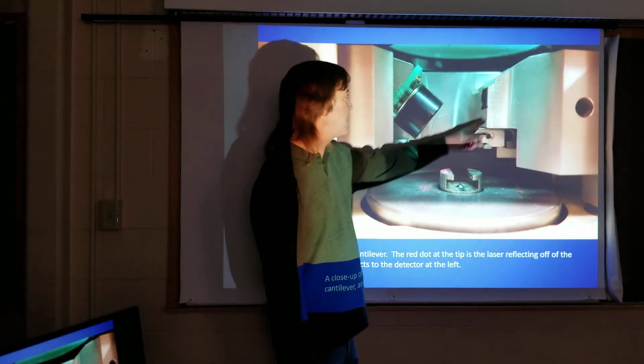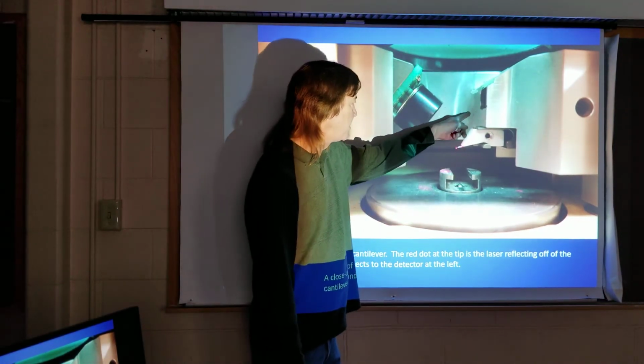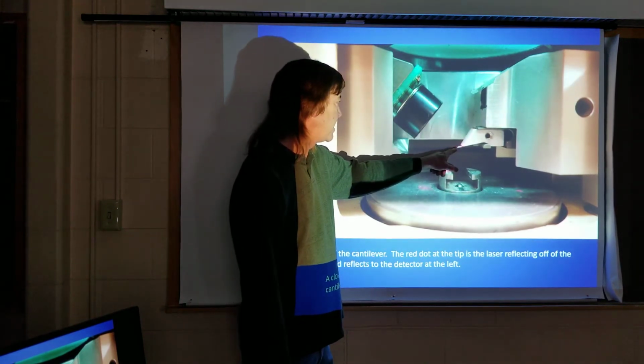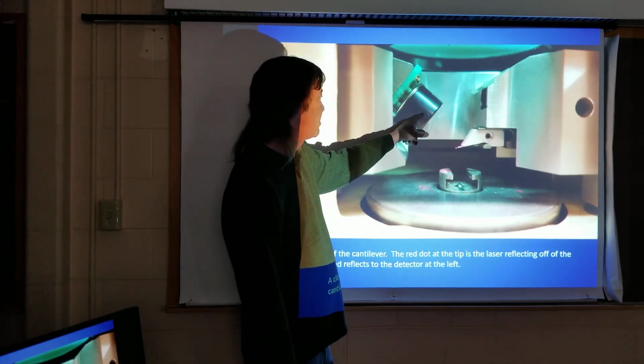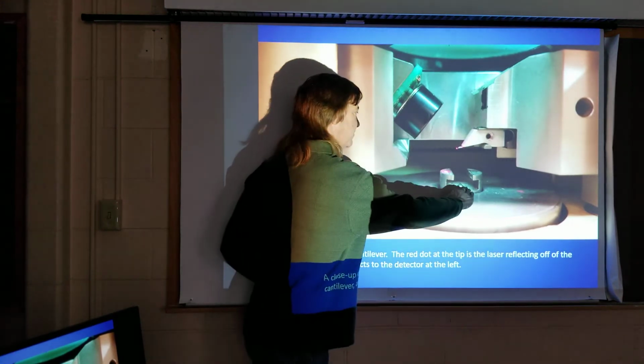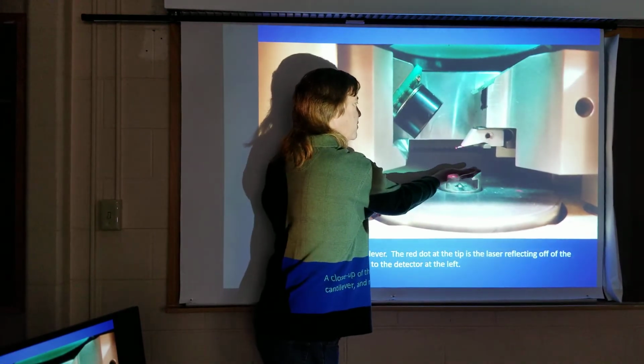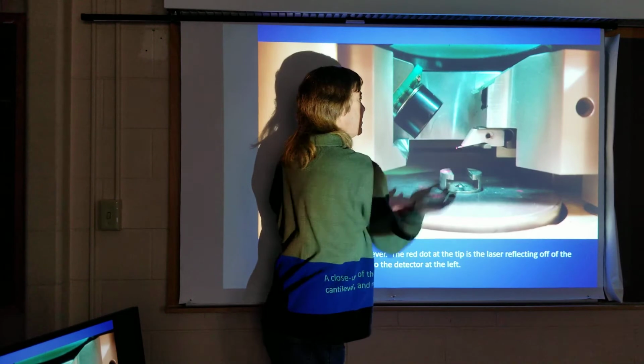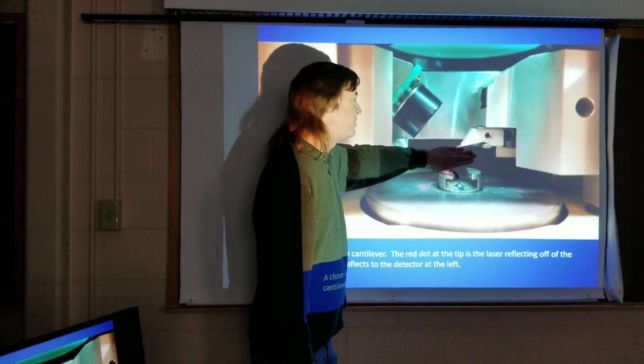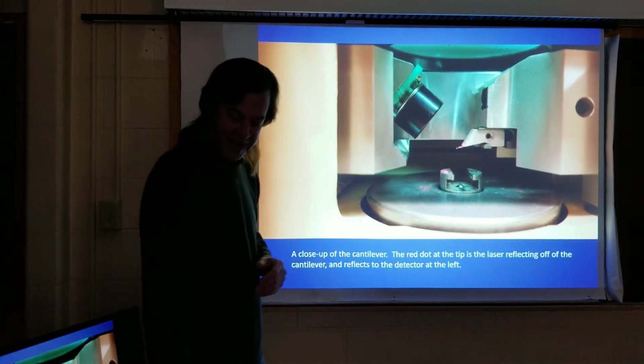Here shows another close-up. You can see here that that's where the laser comes from. There's the mirror. There's where it hits the tip. And then here's where we line it up to our detector. Again, the sample just slides right on in here. And then, of course, we raise it up. And so that way we're actually right underneath the tip of the cantilever, and it can do its scan.